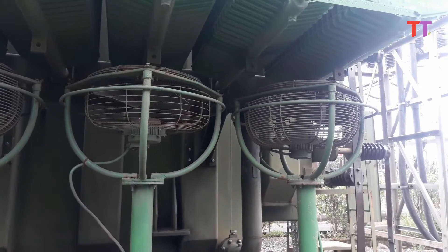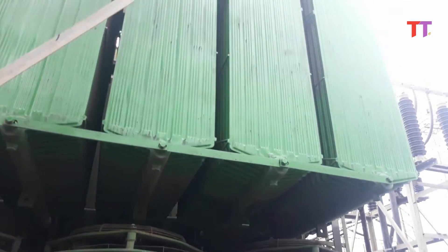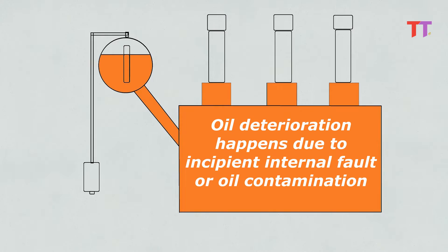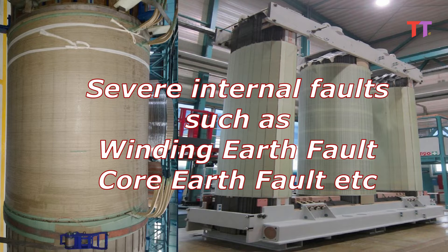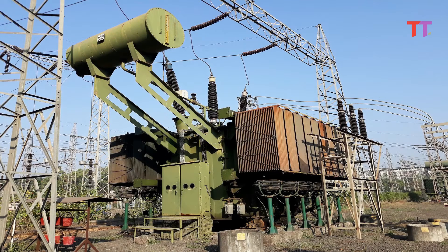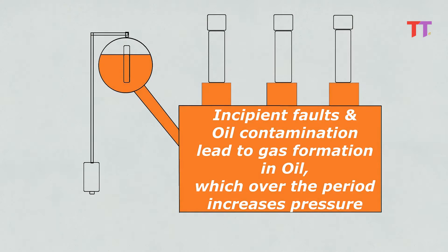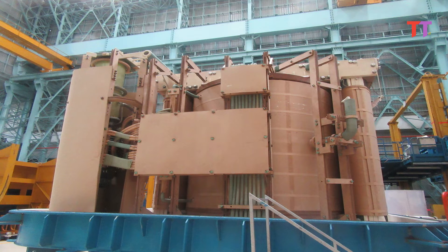In the first case, temperature of oil rises due to cooling system failure or transformer overloading, and oil deterioration happens due to incipient internal fault or oil contamination. In the second case, severe internal faults occur such as winding earth fault, core fault, etc. Due to all such mentioned cases, pressure inside the transformer increases. Incipient faults and oil contamination lead to gas formation in oil, which over the period increases pressure.